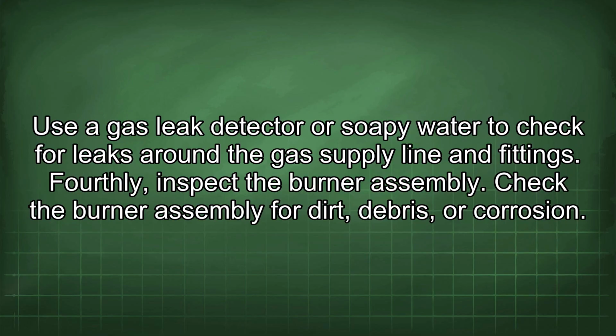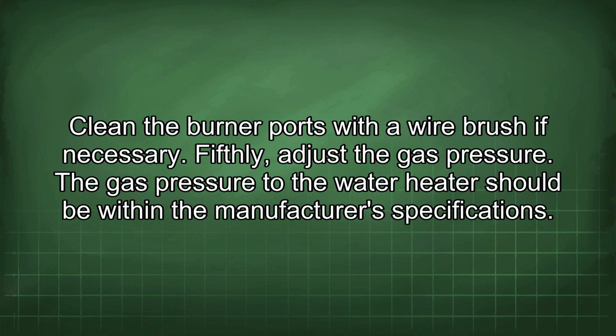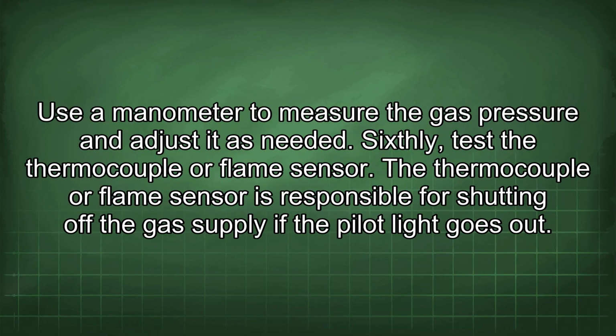Fourthly, inspect the burner assembly. Check the burner assembly for dirt, debris, or corrosion. Clean the burner ports with a wire brush if necessary. Fifthly, adjust the gas pressure. The gas pressure to the water heater should be within the manufacturer's specifications. Use a manometer to measure the gas pressure and adjust it as needed.